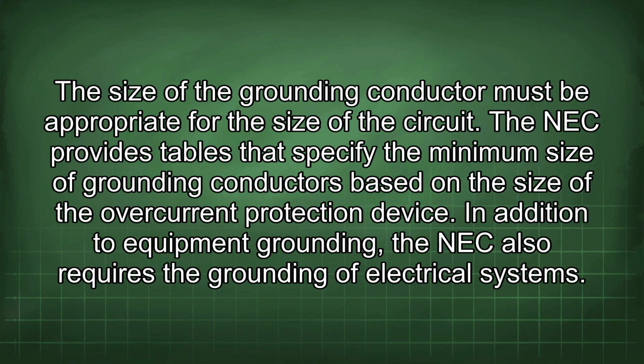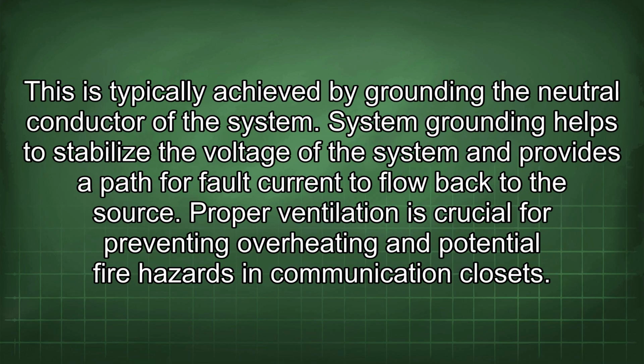The size of the grounding conductor must be appropriate for the size of the circuit. The NEC provides tables that specify the minimum size of grounding conductors based on the size of the overcurrent protection device. In addition to equipment grounding, the NEC also requires the grounding of electrical systems. This is typically achieved by grounding the neutral conductor of the system.